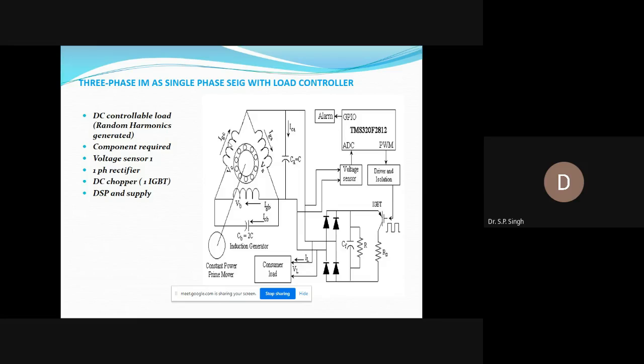So in that case, during the lean period, what can be done is we can alternate the connections of this machine. The delta connected machine can be connected into star, and in case of star the current will decrease by root 3 times. When there is a decrease in the input, we have to ensure that the phase current does not exceed the rated current. So its operation in star is limited to 0.5 to 0.8, that is 80% derating of the machine.